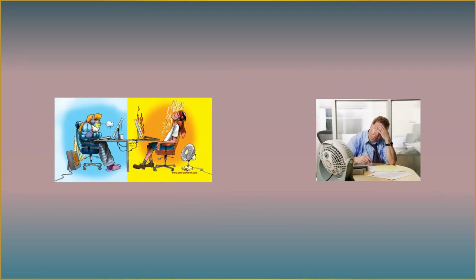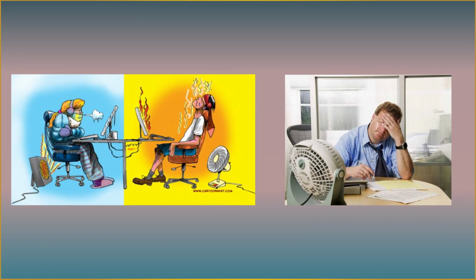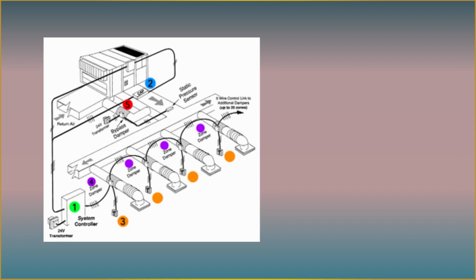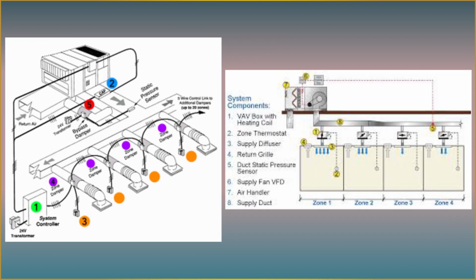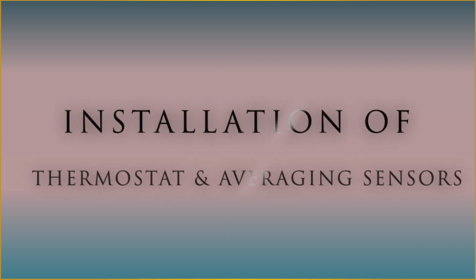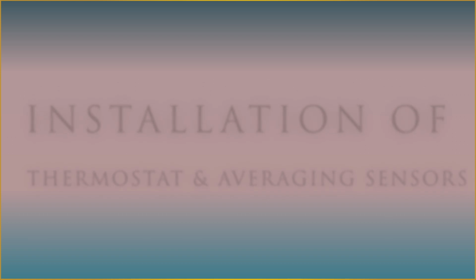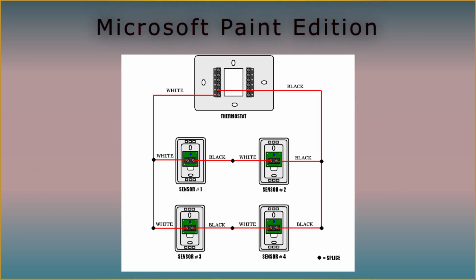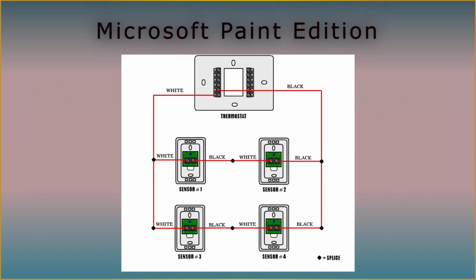If this doesn't work, the only next option would be to upgrade the system to some type of zone system with dampers or VAVs. This is a cheaper method, but it is not a fix-all. Now on to the installation of the thermostat and the 4 averaging temperature sensors. Many years ago, I came up with a method for wiring in these sensors. It's the easiest way in my opinion.